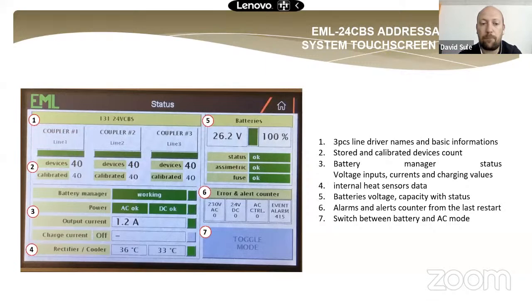At the moment it's 1.2 amp. I think the exit lights were in a maintenance mode, and that's why it shows output current 1.2 amp. And now the charging current is off because the batteries are fully charged. We can see some temperature of the rectifier and the cooler. On number 5, we can see the information of the batteries, the battery voltage, and the remaining capacity of the batteries. The state is okay, and the asymmetry is okay, and the fuse is okay.